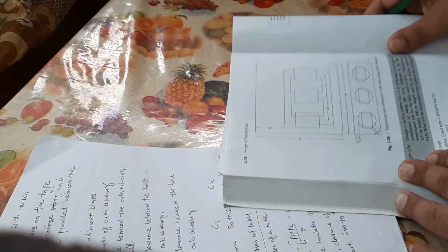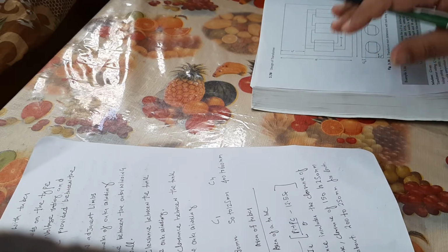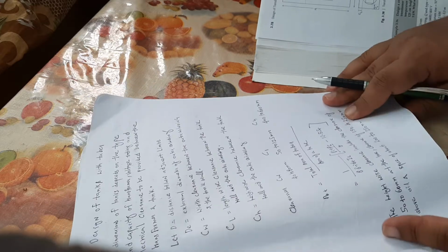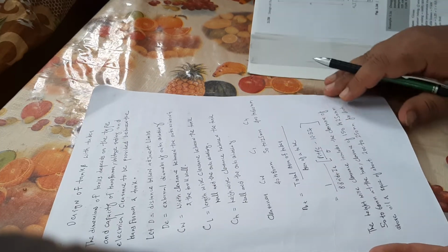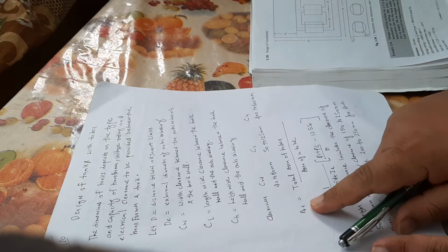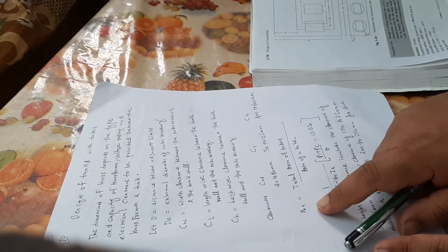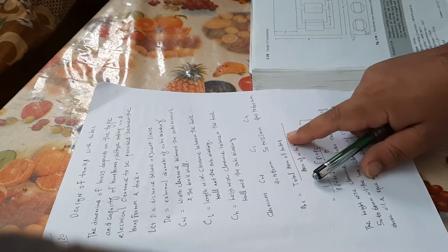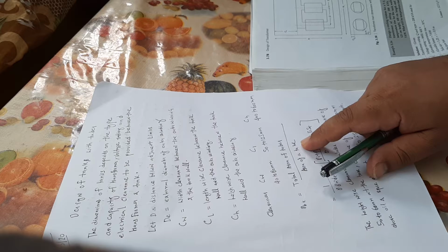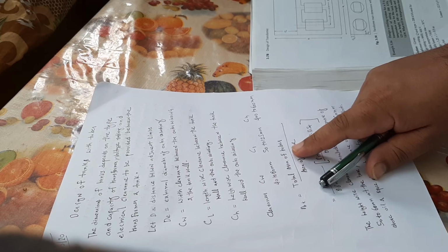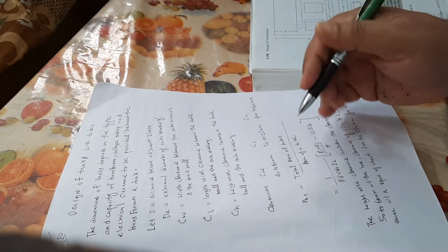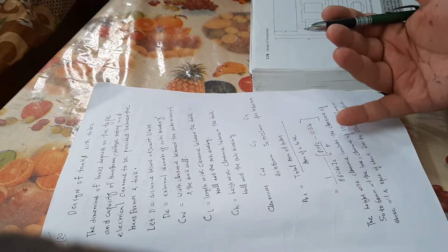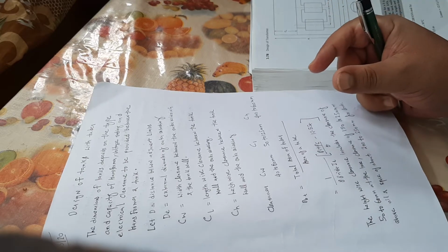So usually, in yesterday's class also, if you go back to that class, we calculated a particular formula for calculating the number of tubes. That was NT equal to the total area of tubes divided by the area of one tube. Total area of what? The total surface area dissipated by the tank and the tubes, divided by the area of one particular tube.